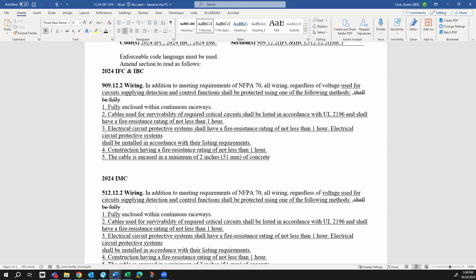I do not have any significant opposition to this option, but those are typically the rating for the cables for smoke control systems, in particular when we're talking about stair or elevator pressurization systems. They're typically addressed in other sections in 909. If we're talking about stair pressurization systems, the requirements for the rating of the cables are already addressed in 909.20.6.1. But this section, 909.12.2, is still applicable because it requires the continuous raceways.